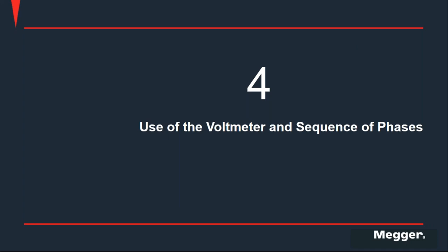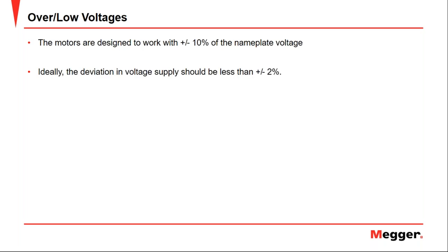Now, why do we have to use the voltmeter? Why is it important? Well, one of the most important aspects to take into account regarding the motor operation is the voltage level of the power supply. That is why the supply voltage must be measured before starting a motor. The NEMA MG1 standard establishes the limits for both over voltage and low voltage in the motor power supply, as well as for voltage imbalance. These aspects must be frequently monitored to avoid damage to the motor when it is in operation.